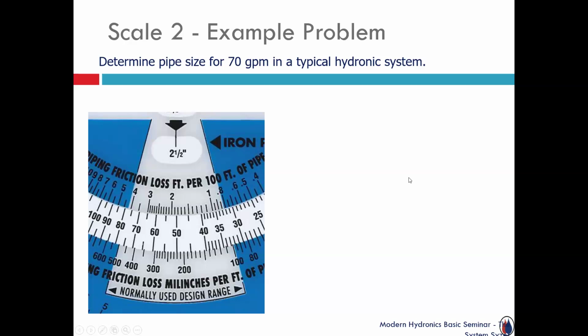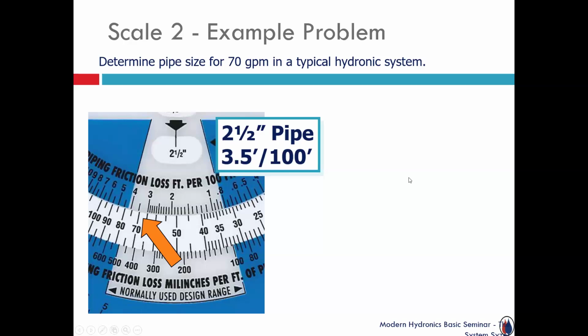So as I scroll through scale 2 and I'm moving the flow rate and lining it up opposite various size pipe, the first pipe that I come across, in this case for iron pipe, is going to be 2.5-inch iron pipe. And that's 70 gallons a minute, falling right here to the left-hand side of that white band. So I could just look at it, read it, and it says, hey, for every 100 feet of pipe, 70 gallons a minute through that 2.5-inch pipe is about 3.5 feet of frictional resistance. So I got 100 feet, 3.5. I got 200 at 7 feet, etc.